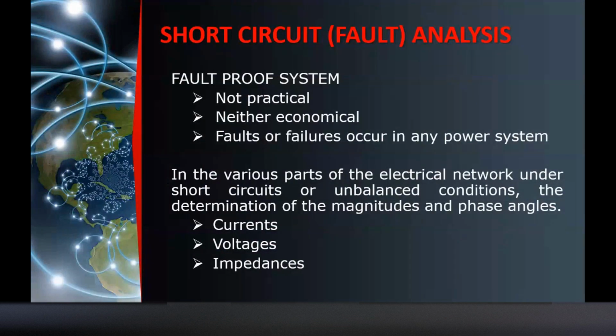So basically, there's no such thing as a fault-proof system. Mahirap, pwede siyang i-attain but not practical because mag-oversize ka ng mga devices mo as well as your equipment. It is neither economical, and hindi natin maiiwasan na faults or failures occur in any power system. So kahit anong sabihin natin, talagang mag-a-occur ang fault. According to experience, faults usually surface out after about 5 years of operation of a brand new plant. After 5 years of operation, maaaring bumaba yung mga insulation level ng mga equipment mo dahil maaaring nagkaroon ng internal fault. So definitely talagang magkakaroon ka ng fault or failures.